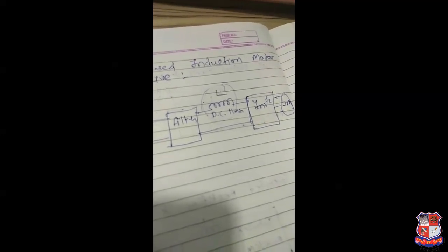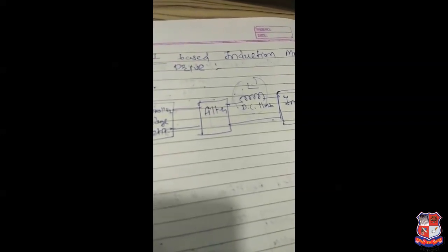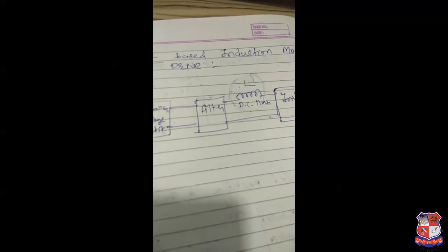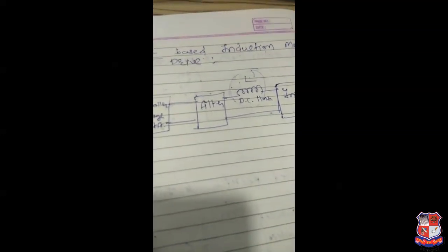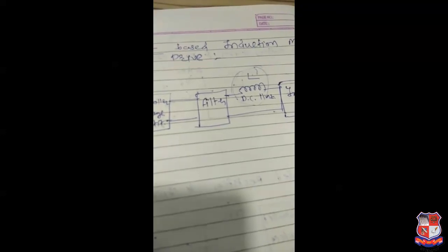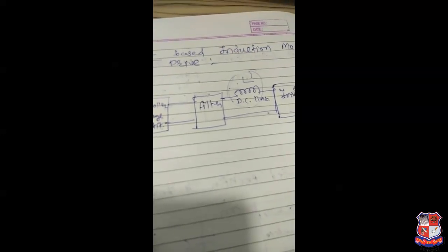The controlled bridge rectifier converts AC into DC, and since the rectifier output contains harmonics, a filter is added in the circuit to remove these harmonics. This DC is fed to the current source inverter and is converted to variable frequency AC to be given to a three-phase induction motor.